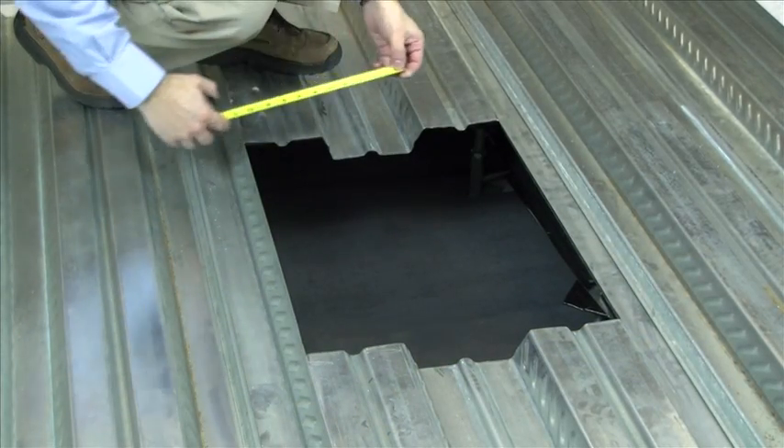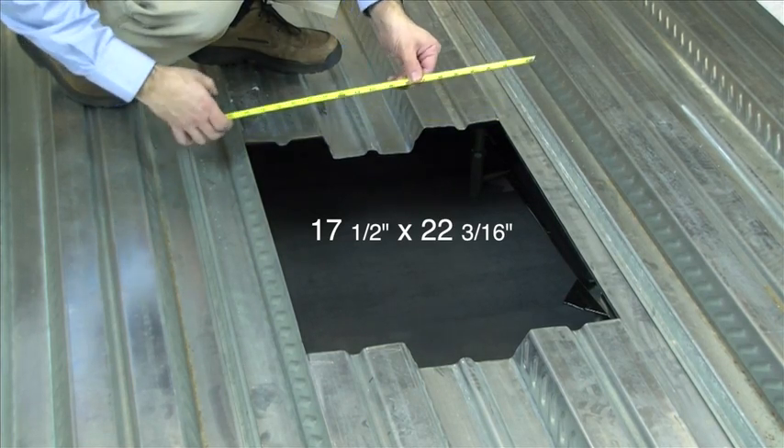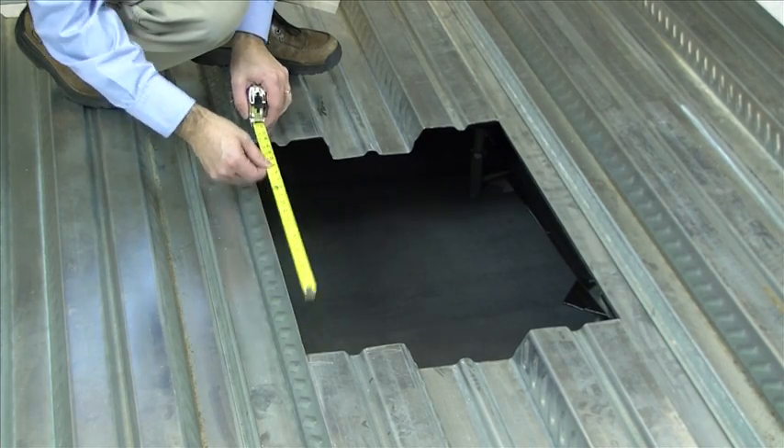Measure and cut an opening into the pan deck 17.5 inches by 22 3/16 inches. Make sure the center line of the box will align with the center of the valley of the deck before cutting the opening.